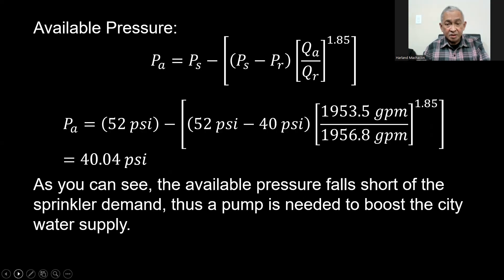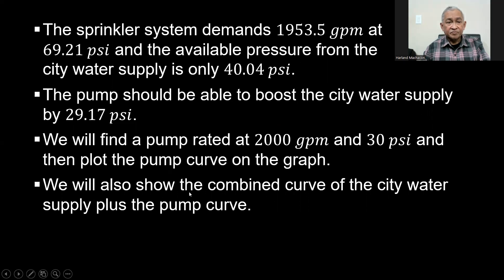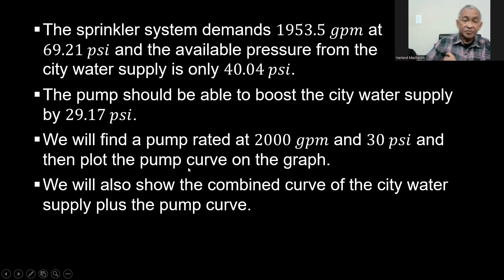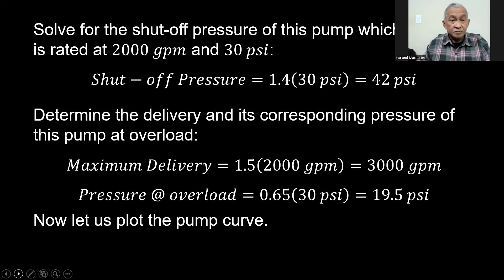So we need a pump to boost the city water supply. The sprinkler system demands 1,953.5 GPM at 69.21 PSI, and the available pressure from the city water supply is only 40.04 PSI. The pump should be able to boost the city water supply by 29.17 PSI. So we will find a pump rated at 2,000 GPM and 30 PSI, and then plot the pump curve on the graph. We will also show the combined curve of the city water supply plus the pump curve. The churn pressure of this pump is 1.4 times the rated pressure: 1.4 × 30 = 42 PSI.